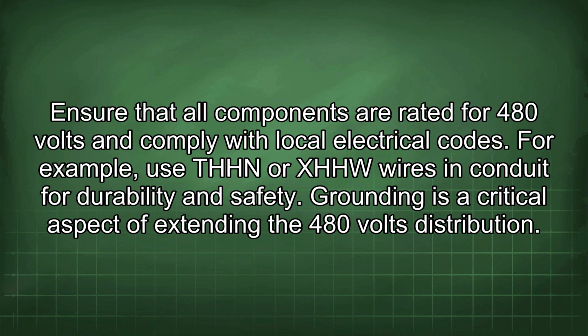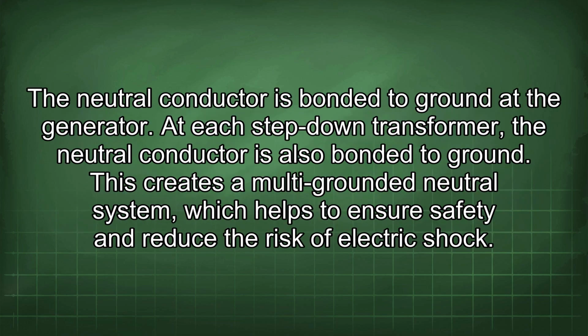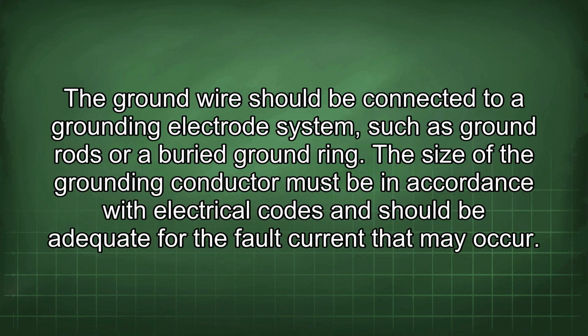Grounding is a critical aspect of extending the 480 volts distribution. The neutral conductor is bonded to ground at the generator. At each step-down transformer, the neutral conductor is also bonded to ground. This creates a multi-grounded neutral system, which helps to ensure safety and reduce the risk of electric shock. The ground wire should be connected to a grounding electrode system, such as ground rods or a buried ground ring. The size of the grounding conductor must be in accordance with electrical codes and should be adequate for the fault current that may occur.